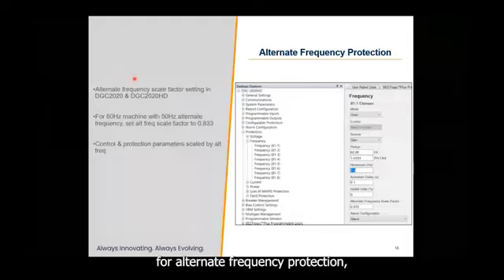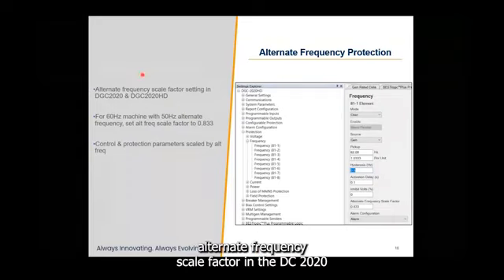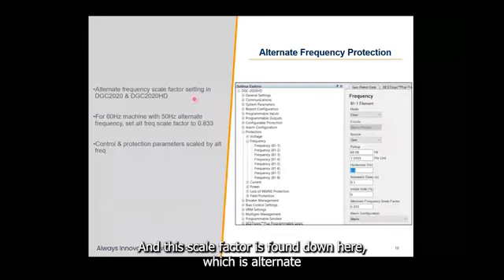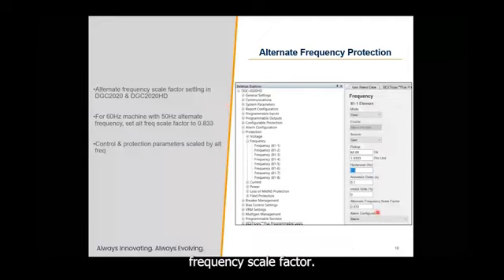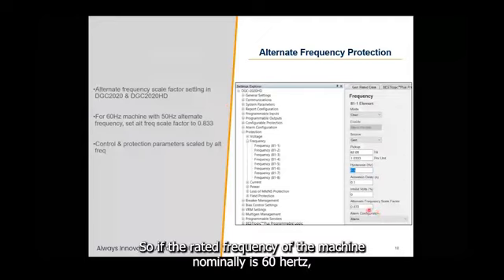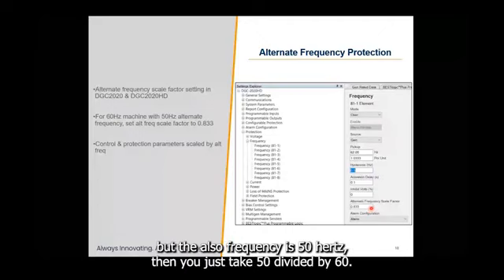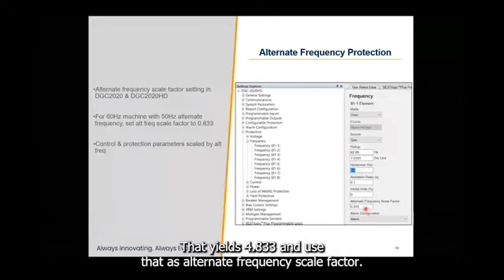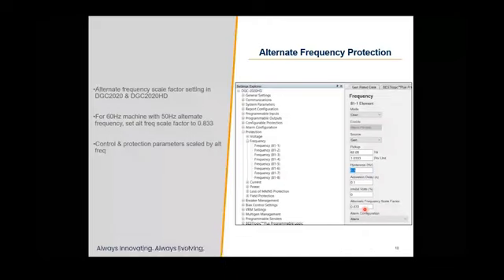For alternate frequency protection, there is an alternate frequency scale factor in the DGC 2020 as well as the 2020 HD. And this scale factor is found down here where it says alternate frequency scale factor. So if the rated frequency of the machine, nominally it's 60 hertz, but the alternate frequency is 50 hertz, then you just take 50 divided by 60, that yields 0.833, and use that as your alternate frequency scale factor.